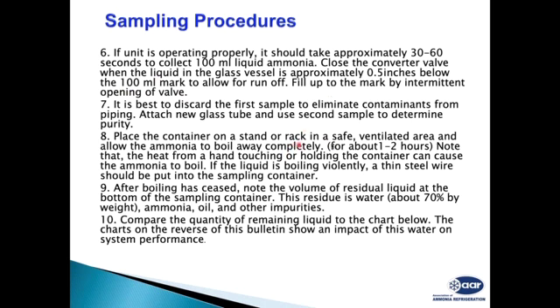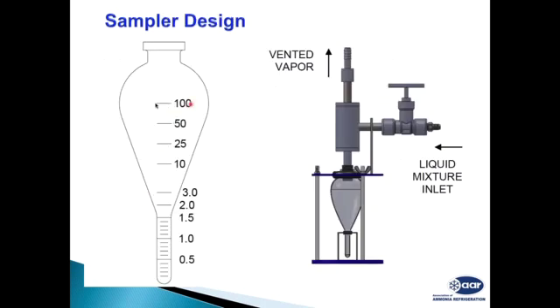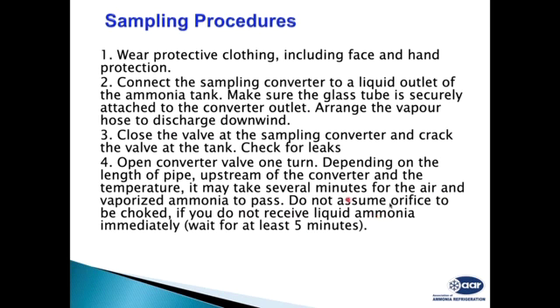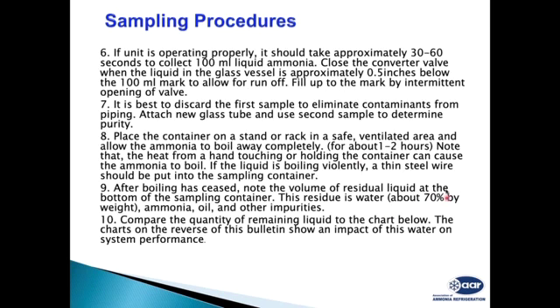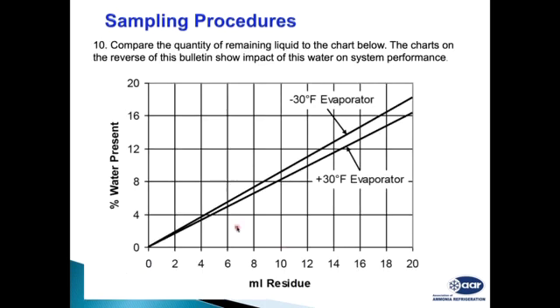Place the container in a safe stand or rack in a ventilated area. Allow the ammonia to boil out completely. It will take 1 to 2 hours to boil out the ammonia. Once the ammonia has boiled out, to measure the residual quantity, we have this beaker with the 100 ml sample, and whatever ammonia there is will boil out. Normally 70% of this content is actual water; the rest may be oil and other impurities. You can use this chart to check the residuals depending on the temperature, maybe minus 30 or plus 30 degrees Fahrenheit. It will give you the percentage of water.